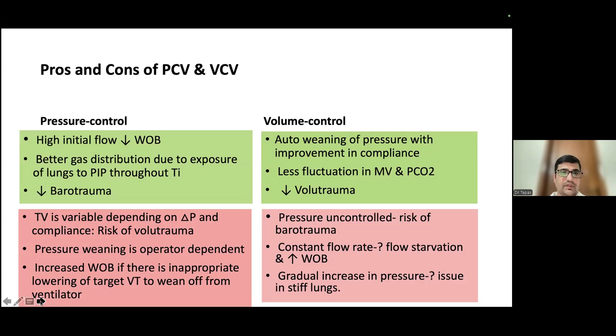Now the question comes, why is there increasing interest in using volume ventilation in newborns? If you go back some 3 decades, in the previous volume control ventilators, the flow sensor was actually inbuilt within the machine itself. So the flow sensor was distal, within the machine itself. This machine injects the tidal volume into the circuit, which is measured by the flow sensor. However, this gas which is injected into the circuit will undergo some amount of compression in the circuit, as well as within the humidifier, and these circuits are compliant. They are distensible circuits.